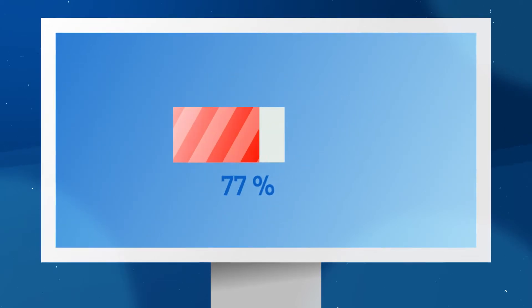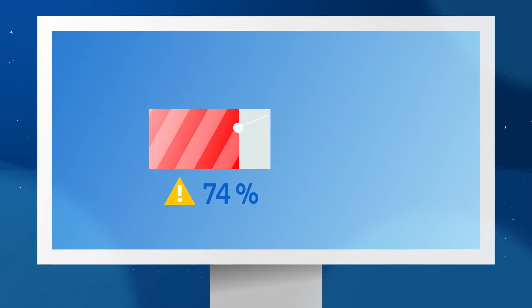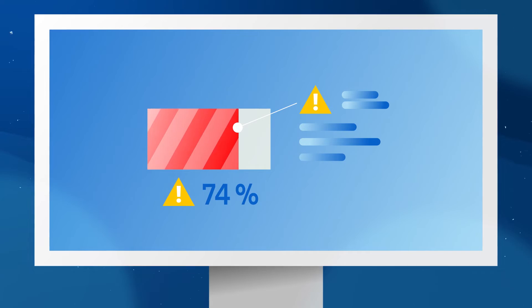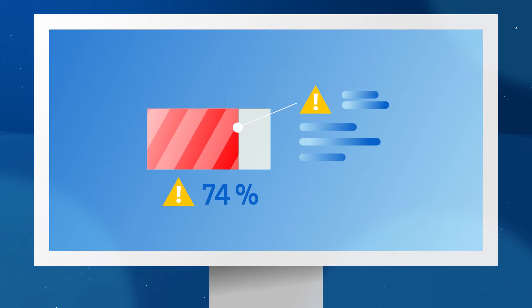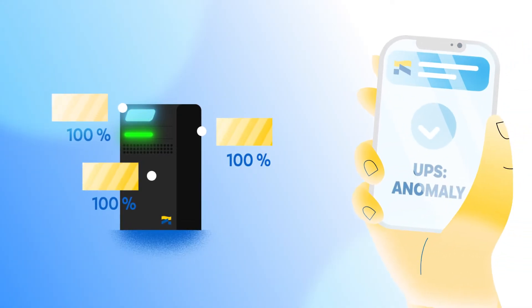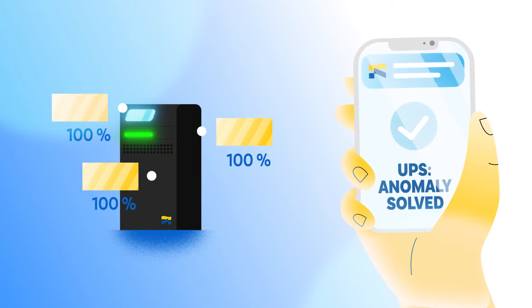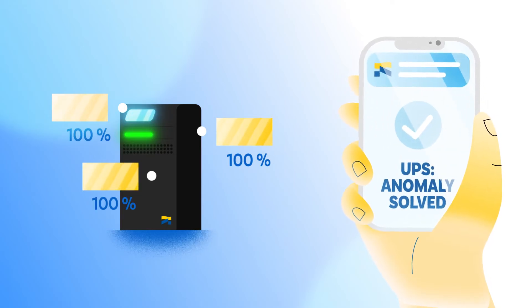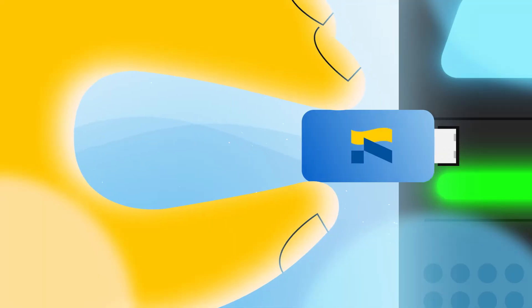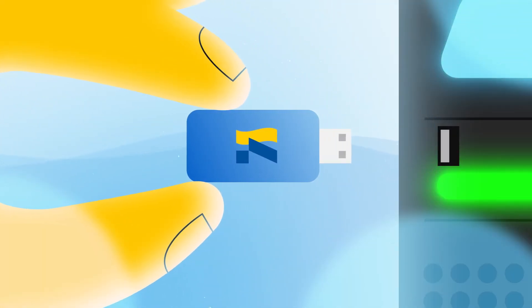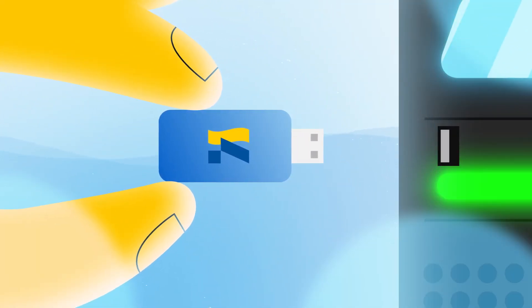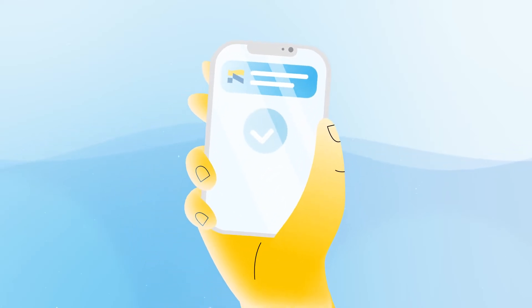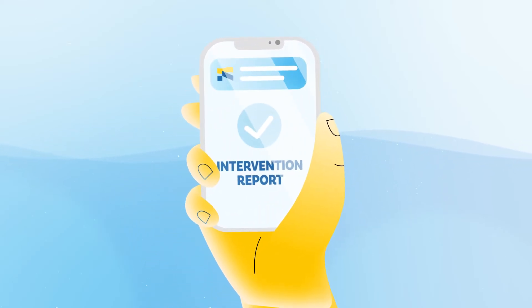The root cause has been identified and all the necessary restoration tasks that could be carried out remotely have been completed, including the adjustment of parameters and alarm reset. The anomaly has been resolved, and the UPS is no longer in alarm mode. At the end of the remote session, Anna removes the USB Bluetooth dongle and receives the troubleshooting intervention report from Socomec.